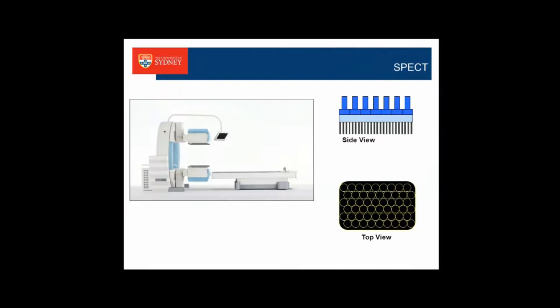And just looking at the basic geometry of a SPECT system, and then we'll look at a PET system. So SPECT systems typically make use of what's called an Anger detector, which has the scintillator. Typically, it's a large area sodium iodide scintillator. Not always. A lot of the preclinical systems are segmented systems, but often in clinical systems, we use large area continuous sodium iodide scintillators.